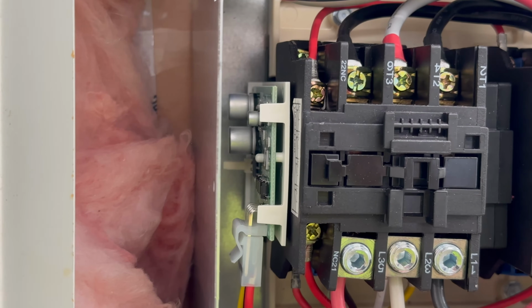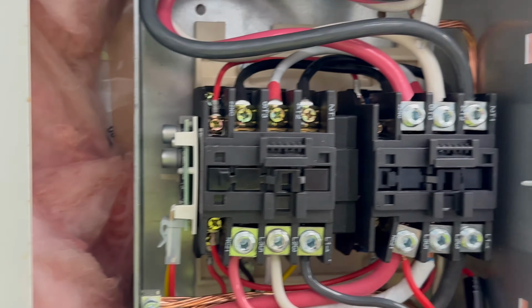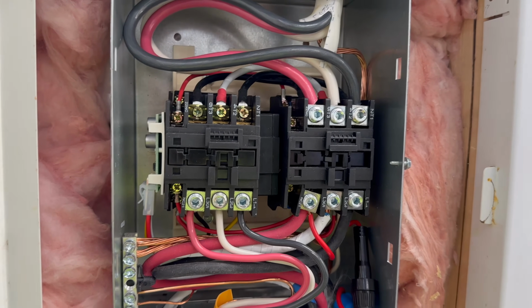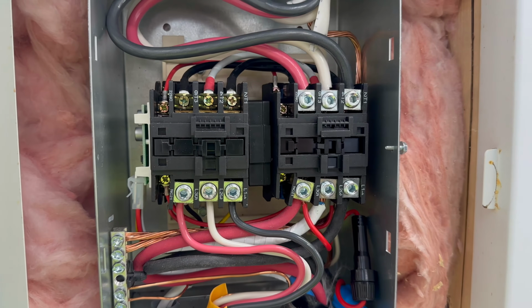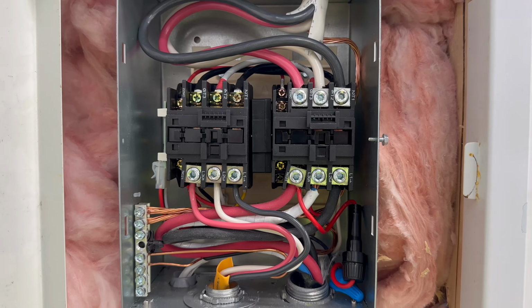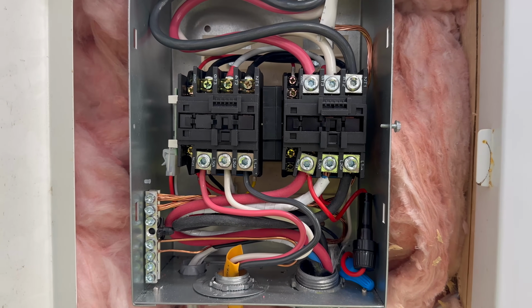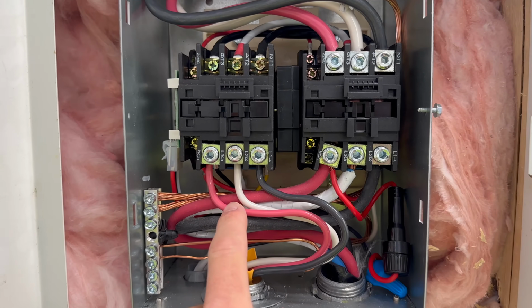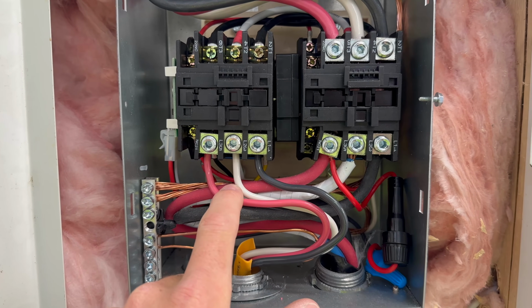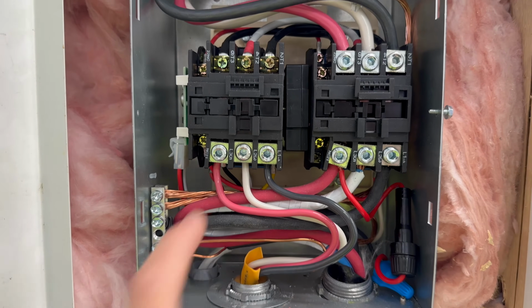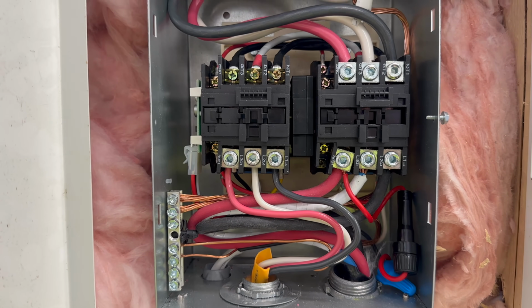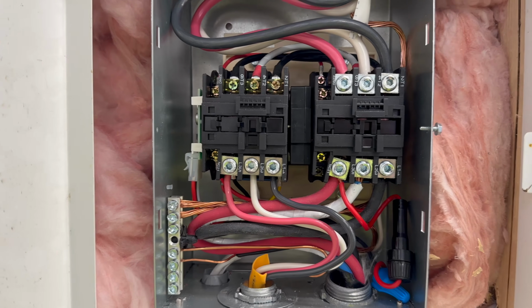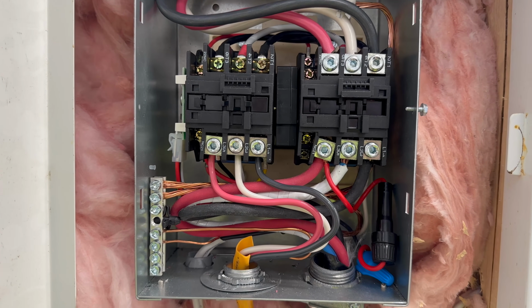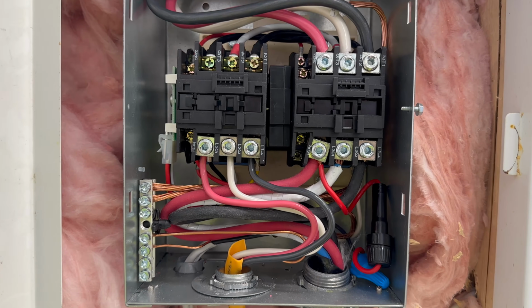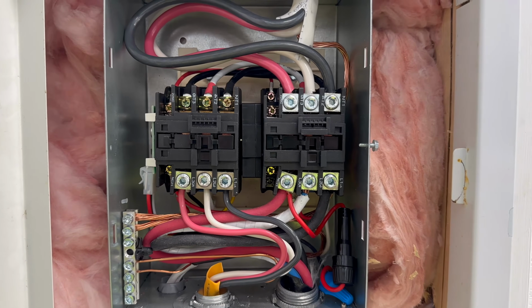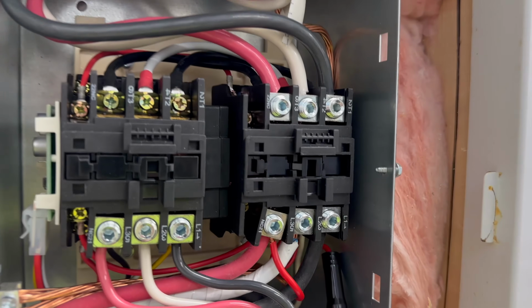There's a small board on the side here which controls some of the functions of it and gives it a time delay that is adjustable should you want that. I have it set at 20 seconds. How that works is once the generator is running and putting out power, this will recognize that there is now power on the generator input, and after 20 seconds of that power being present, it will then transfer over to that generator power. Gives the generator a little bit of time to warm up and get to speed before slamming on all of the load of the building. And then as soon as generator power is lost, it will go right back over to utility power.